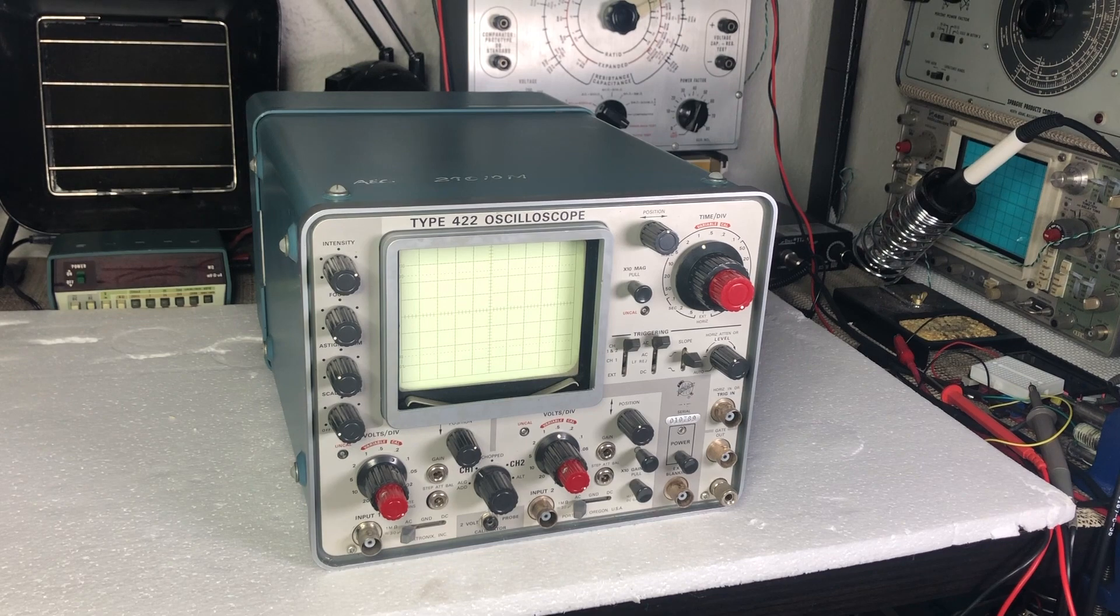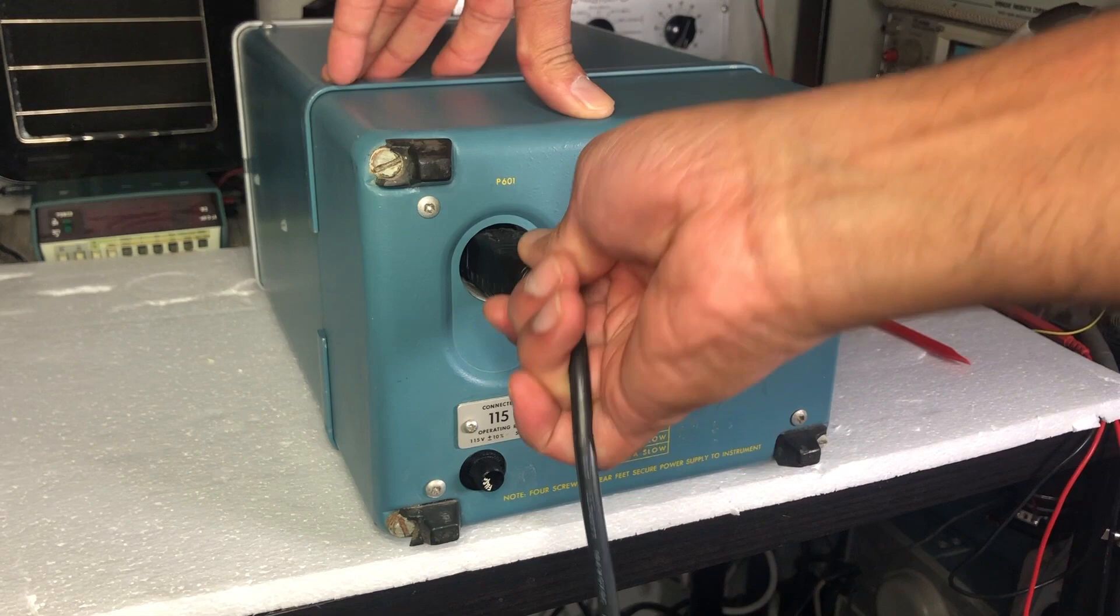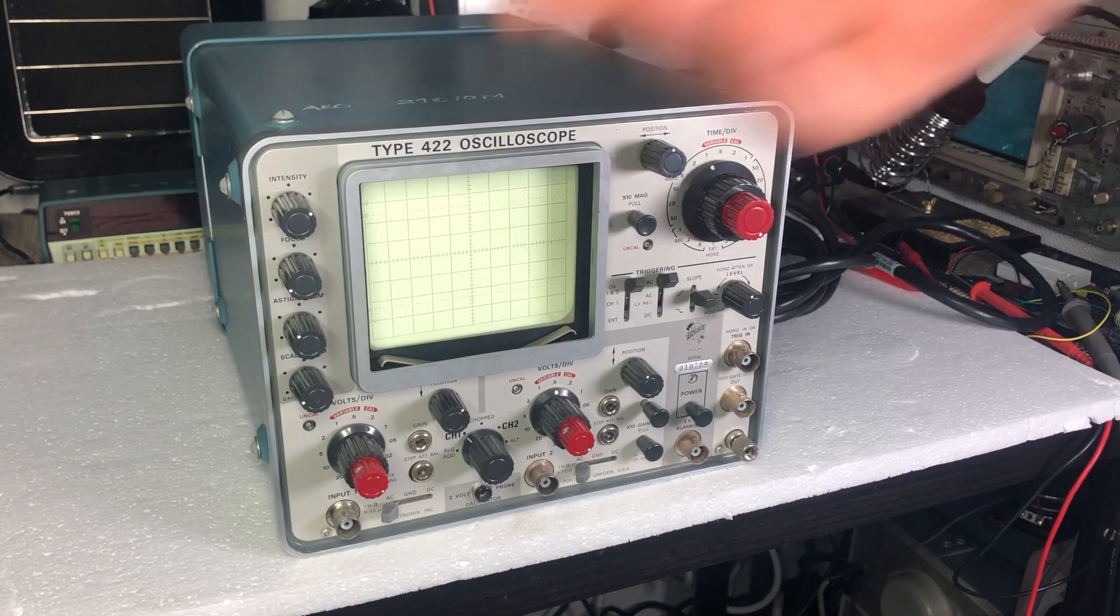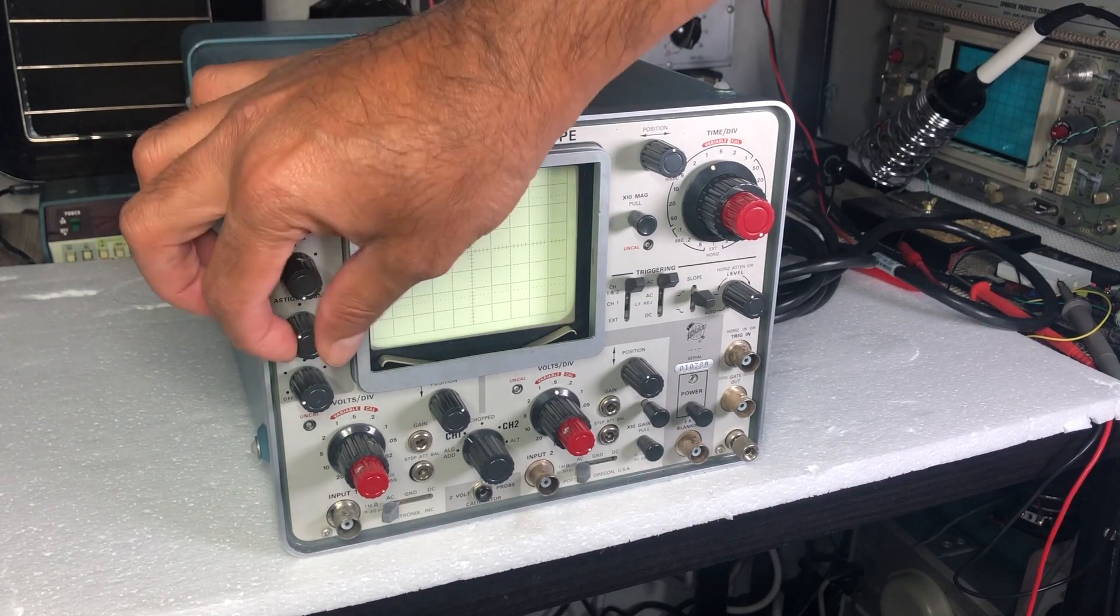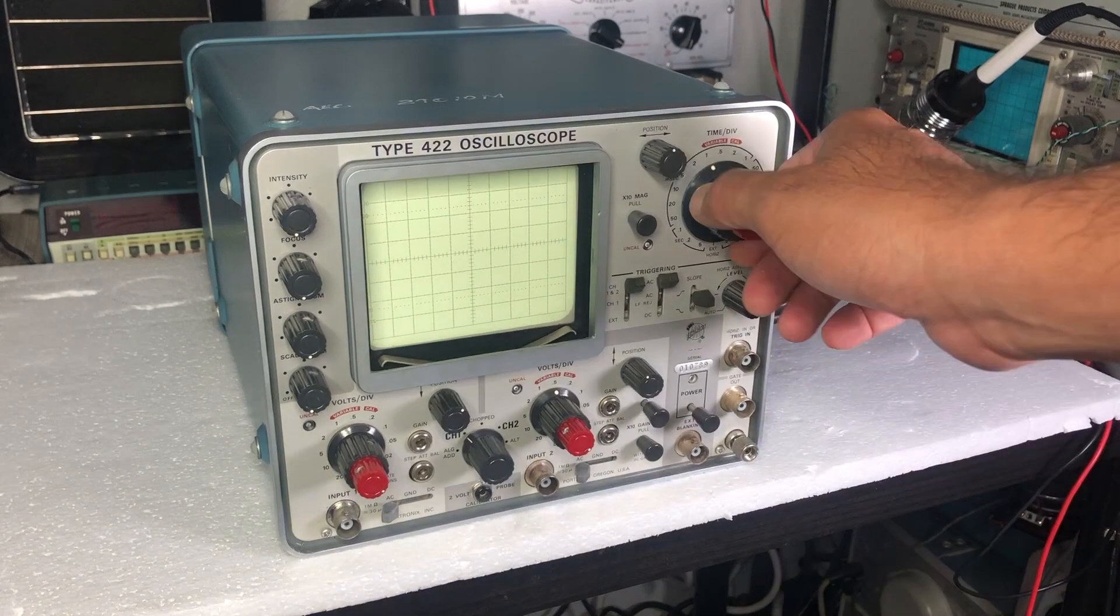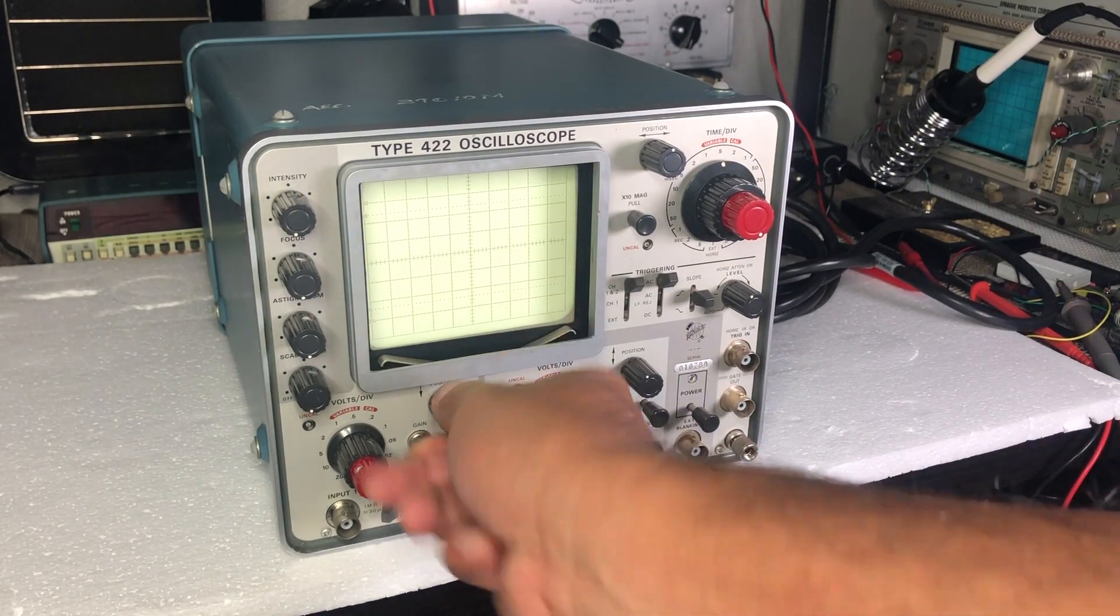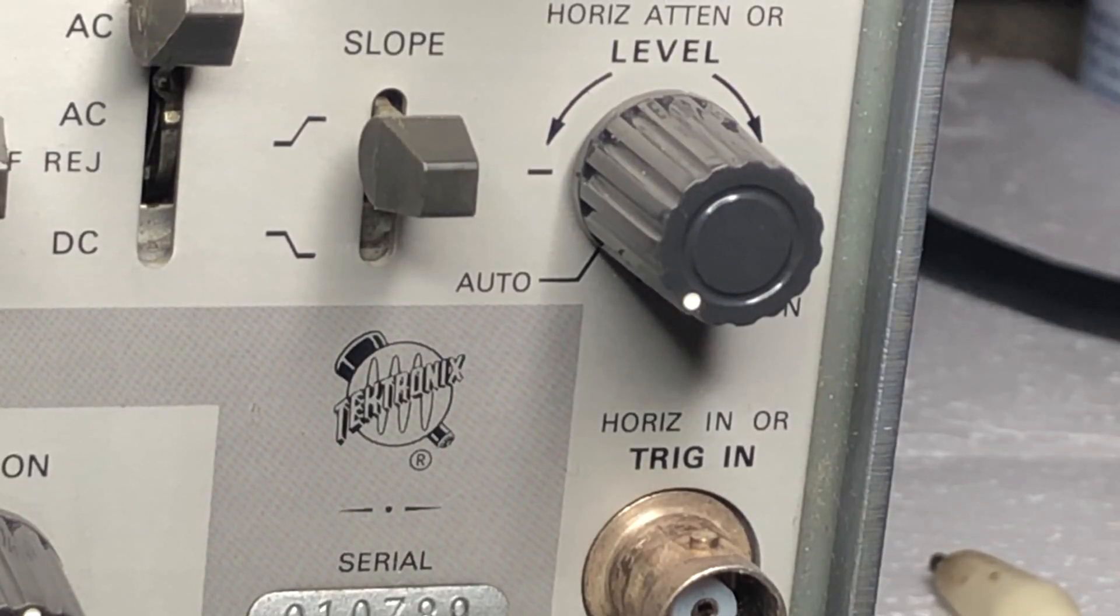I've already tested the fuse and the fuse is good. Pre-power-up checklist: intensity minimum, focus, STIG, scale illumination everything to minimum or counterclockwise. Passage on horizontal sweep maybe at 0.5 millisecond, all the position controls in the mid position. I put it into auto trigger, and let's power it up.